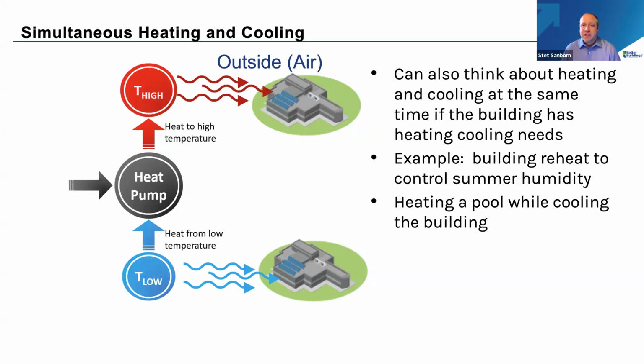And whether you hear these systems called heat recovery chillers, heat recovery heat pumps, simultaneous heating and cooling heat pumps, or lots of other names, these systems are the most efficient. We'll see coefficients of performance, or efficiency values, over 6, sometimes as high as 12. Those systems are exceptionally efficient because you're using, or valuing, both sides of the heat pump. Next slide.